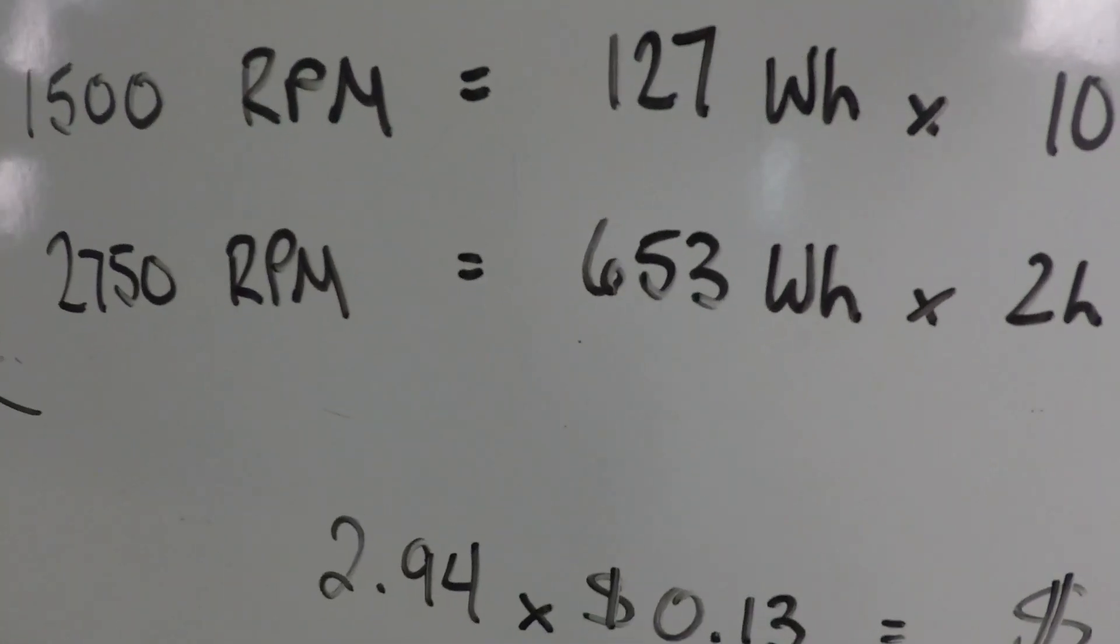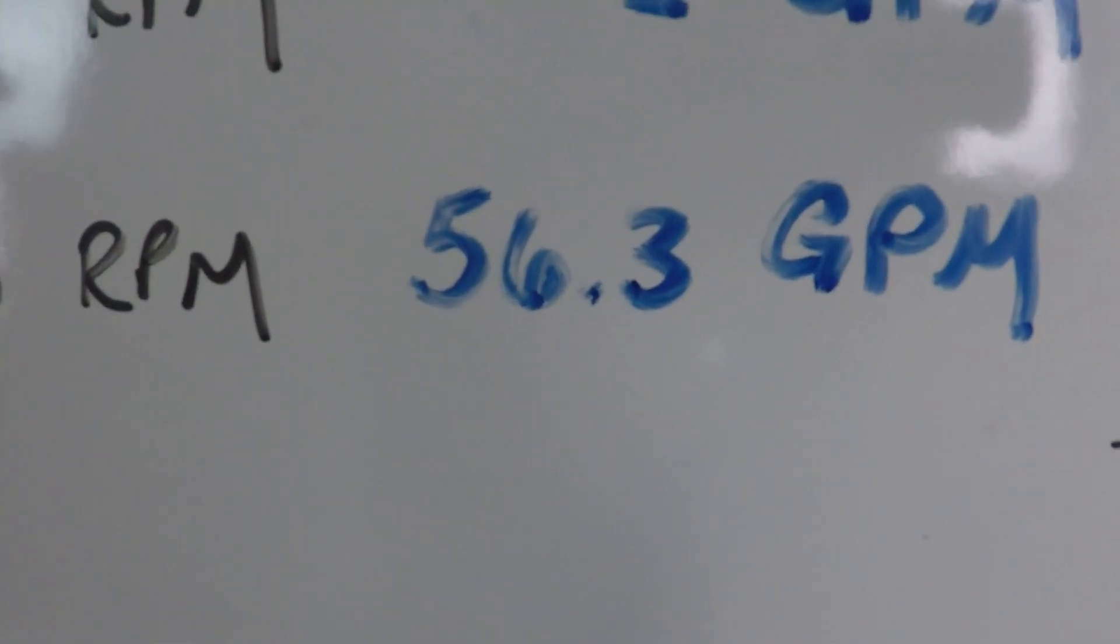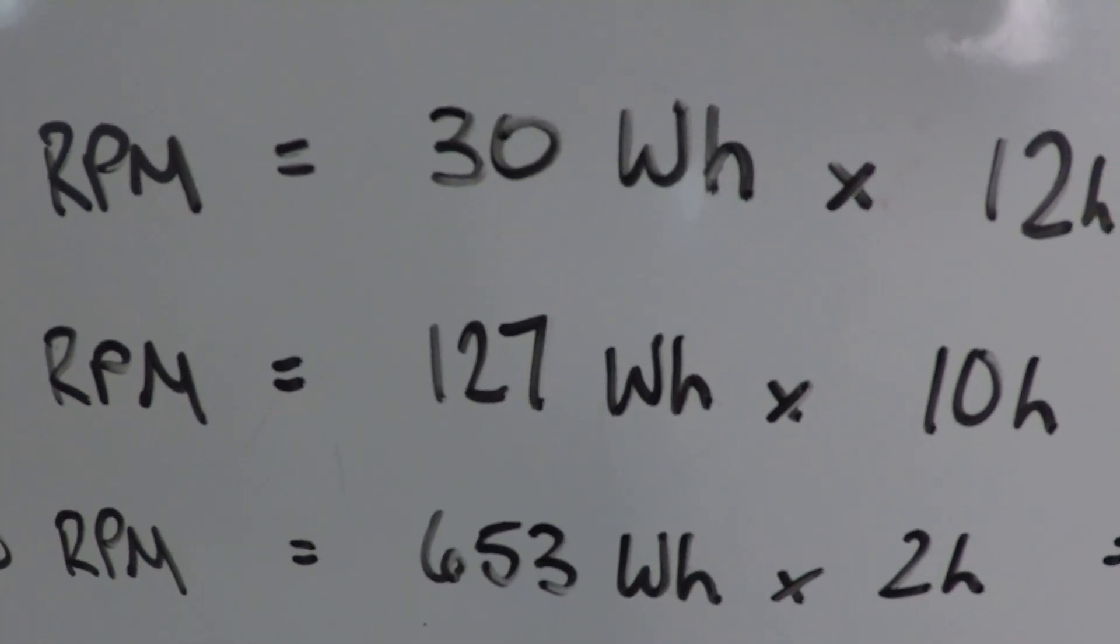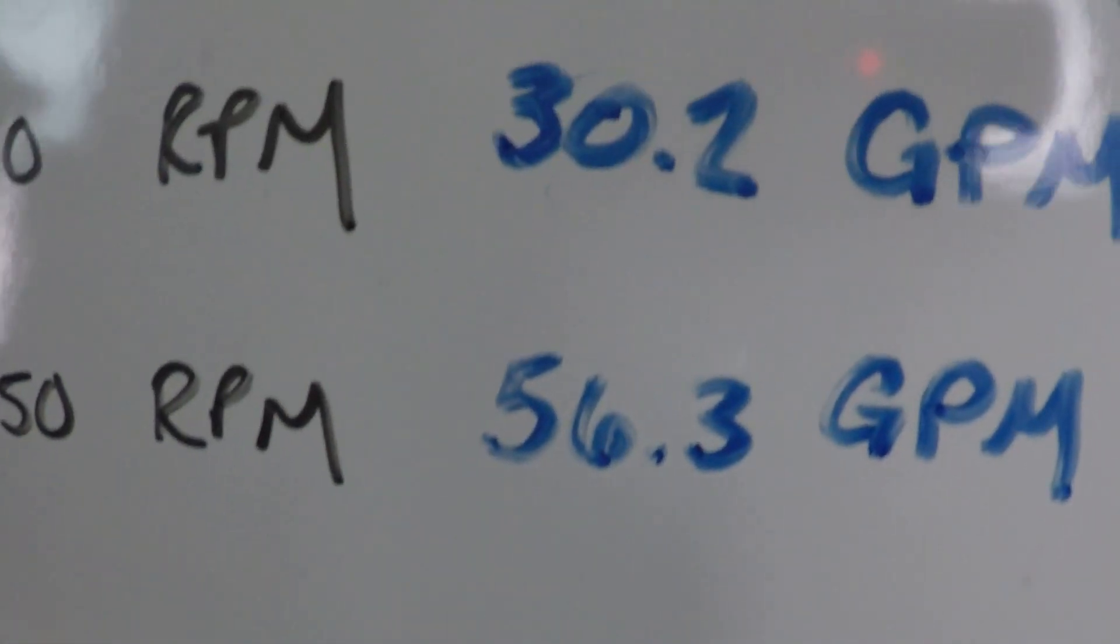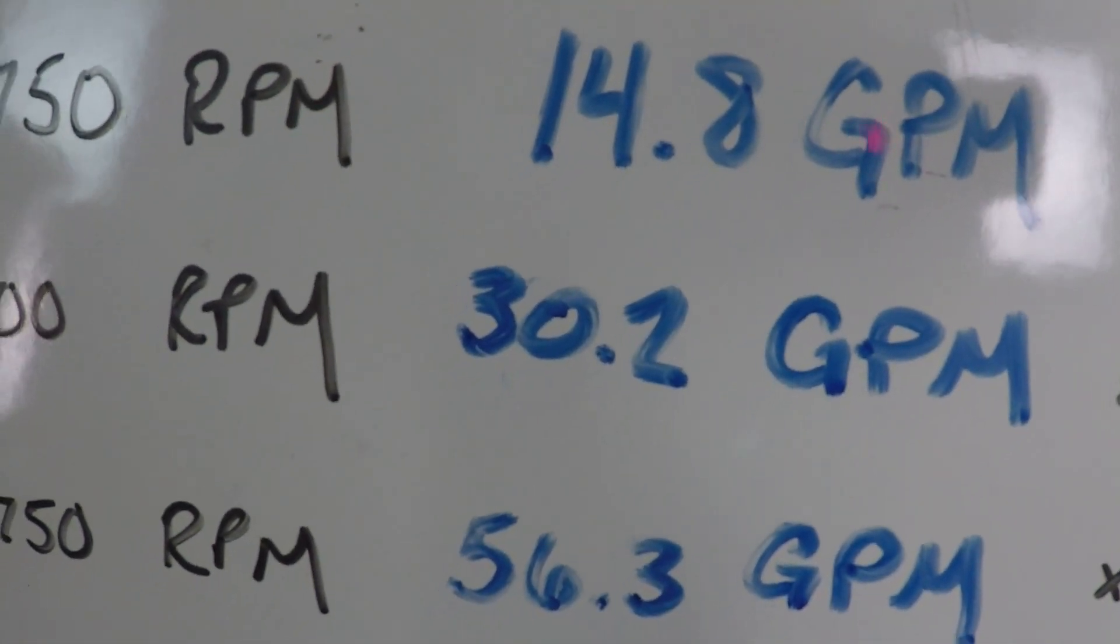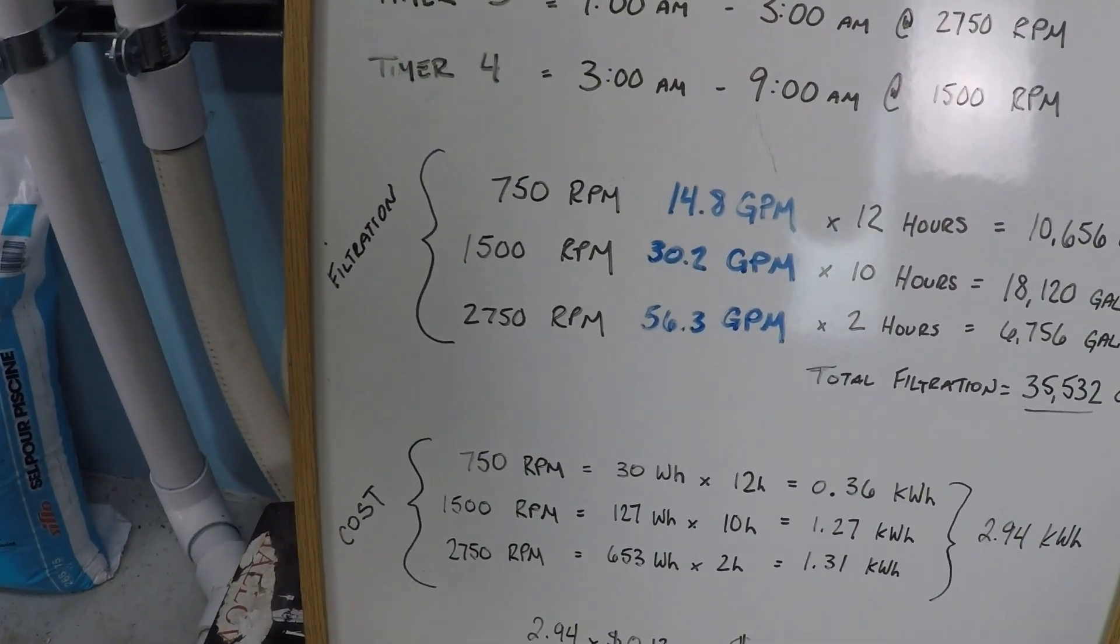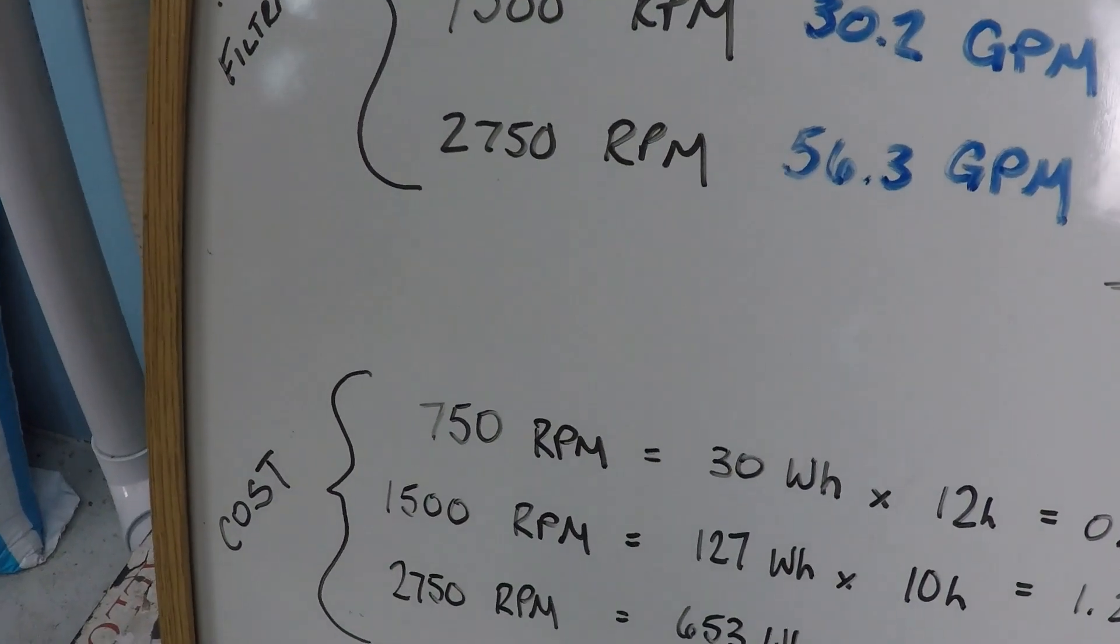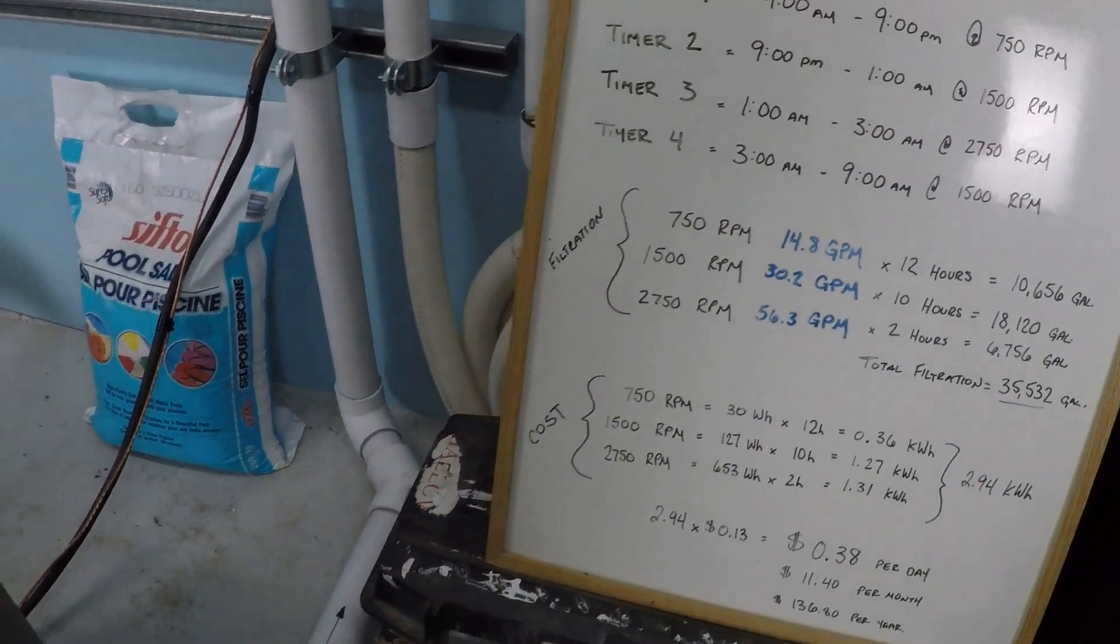And that's very interesting, because at 653 watts per hour, we got 56 gallons per minute. But you cut that wattage way down to 127 watts per hour, we're still getting a shade over 30 gallons per minute. That's how this works. The more you turn it down, the more you save. There's a point of diminishing returns, because you need the pump to be able to overcome the resistance to flow. And you can determine that if you have a flow meter.